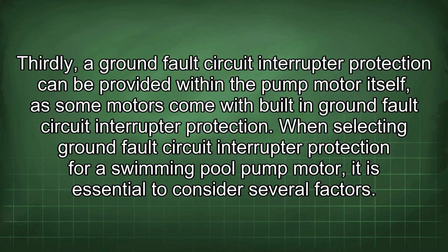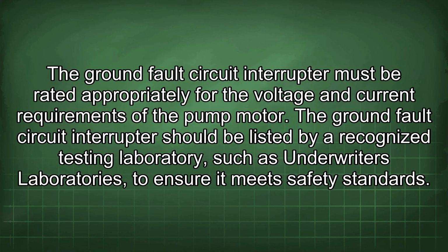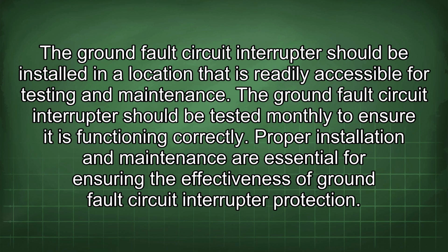When selecting ground fault circuit interrupter protection for a swimming pool pump motor, it is essential to consider several factors. The ground fault circuit interrupter must be rated appropriately for the voltage and current requirements of the pump motor. It should be listed by a recognized testing laboratory, such as Underwriters Laboratories, to ensure it meets safety standards. It should be installed in a location that is readily accessible for testing and maintenance, and it should be tested monthly to ensure it is functioning correctly.